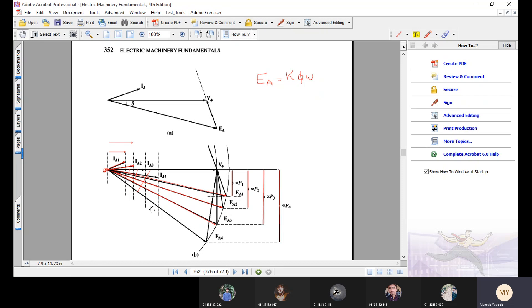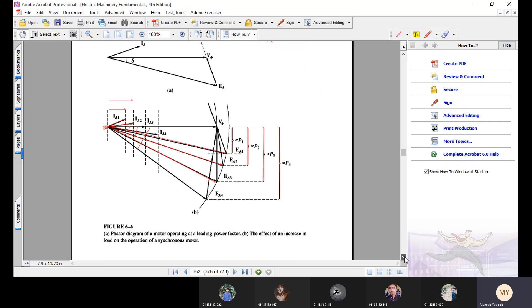In summary, when we increase the load, the speed of the motor remains the same, but the load current increases, the torque angle increases, and the quantities proportional to real power — Ia cos theta and Ea sine delta — will increase, while the magnitude of Ea will remain constant.